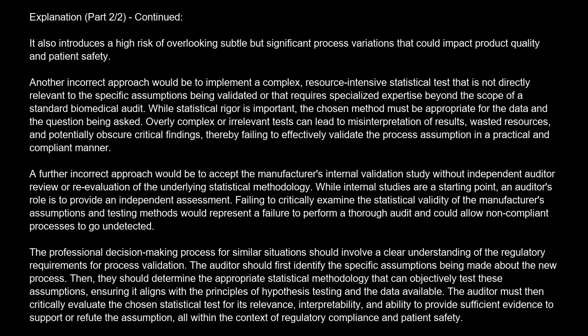A further incorrect approach would be to accept the manufacturer's internal validation study without independent auditor review or reevaluation of the underlying statistical methodology. While internal studies are a starting point, an auditor's role is to provide an independent assessment. Failing to critically examine the statistical validity of the manufacturer's assumptions and testing methods would represent a failure to perform a thorough audit and could allow non-compliant processes to go undetected.